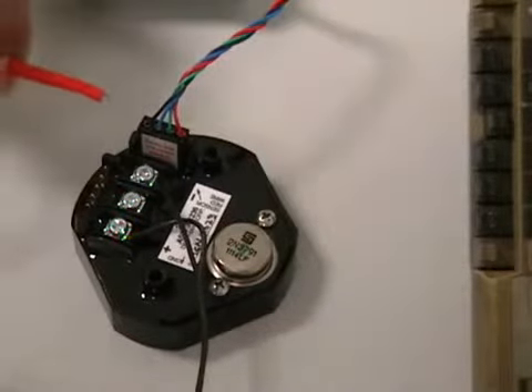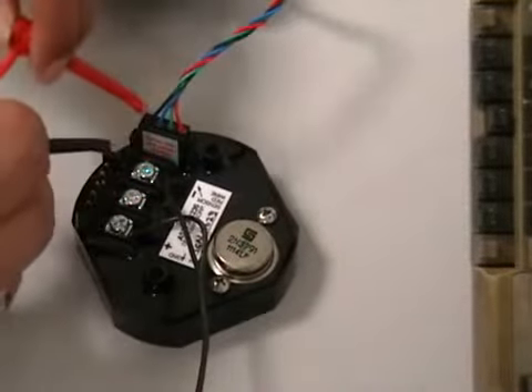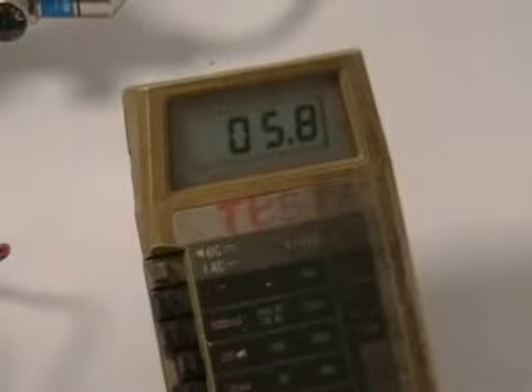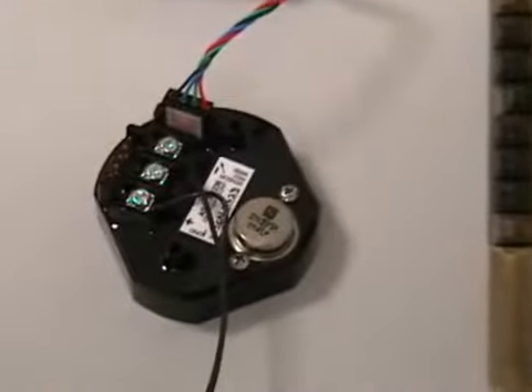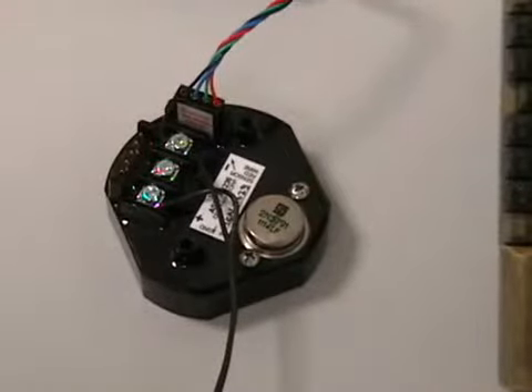To check the operating voltage of a sensor, probe the two outside pins, red and black, on the 4-pin sensor connector plugged into the transmitter. This reading should be between 5.6 and 6.4 volts, depending on the actual sensor elements installed on that sensor.